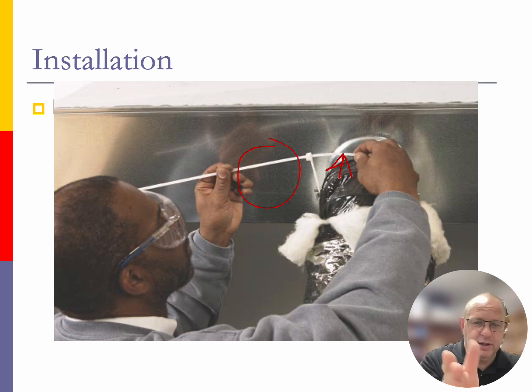Remember, our takeoff was put into the square pipe and it has a damper on it. We're going to stretch this guy over top of that takeoff, and we're going to use draw bands, big wire ties that we're going to take and tighten with a special tool. Do not use your fingers to tighten this. You cannot get it tight enough. You have to use the special strapping tool that goes around this and tightens it.